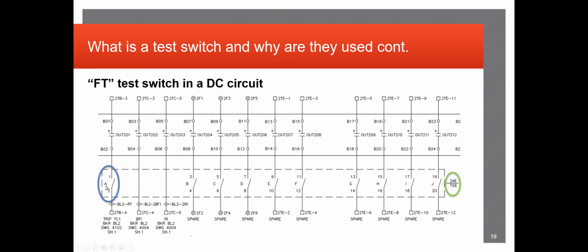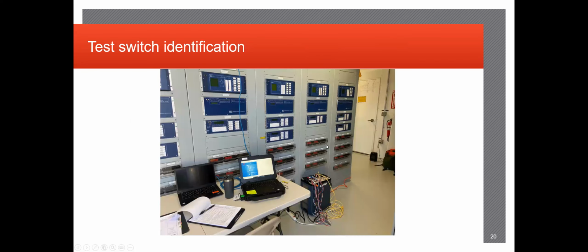The test switches you'll usually see out in the field, again, if they're associated with these relays, they'll probably be labeled either 1 through 10. Usually you'll see either 10 or 12 test switches per mounting bracket, or you'll also more commonly probably see A, B, C, D, E, et cetera, et cetera. In this picture right here, you can kind of see how this actually didn't plug in any test switches. It's weird, unless it's under the table. But you can identify all the relays up here and their associated test switches right at the bottom.